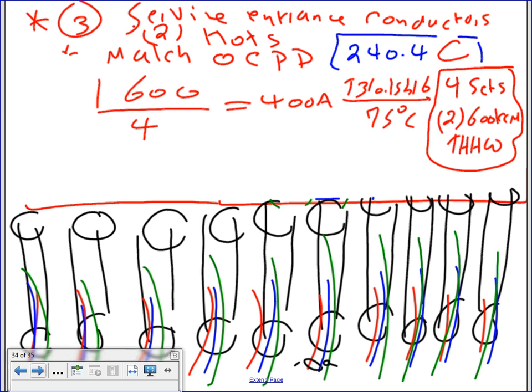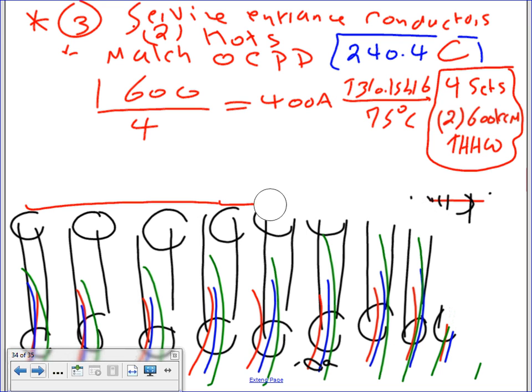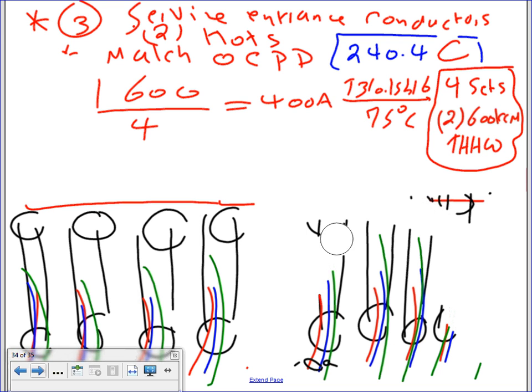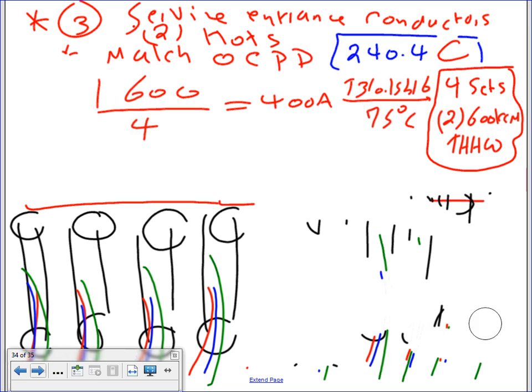So you divide it by 4. Because I'm just seeing that on the last example that you did, you divided it by 10, because we were paralleling 10 sets. I'm erasing it right now. How many sets can you parallel? Remember, guys, when you parallel, you will end up with a number here that's close to 400 amps. What was the size that we did last time? It was 3,000. Divide by 10 will give you 300. You're going to hover around 400 amps when you parallel.